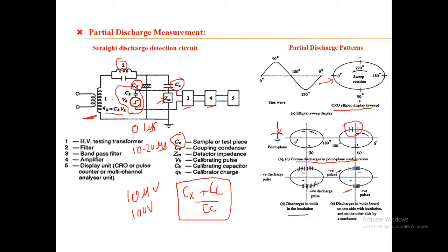Another method of calibration is to use the secondary standard consisting of a point hemispherical electrode system of specified dimensions, as denoted by IEC 270, 1968. This method is more accurate and easily reproducible with the point hemisphere geometry as compared with the point plane, so an accuracy of 10 to 20% can be obtained.